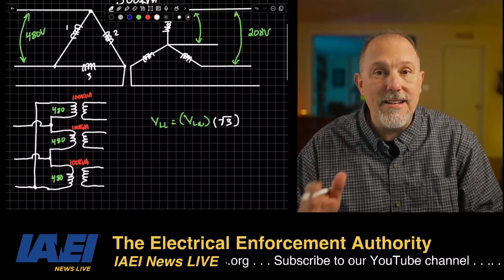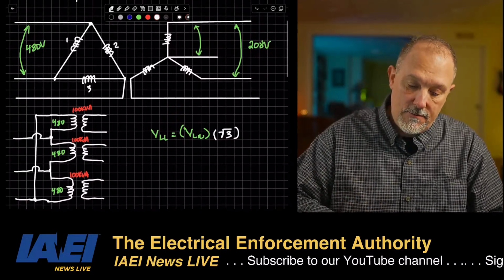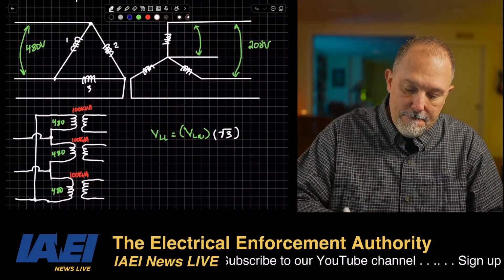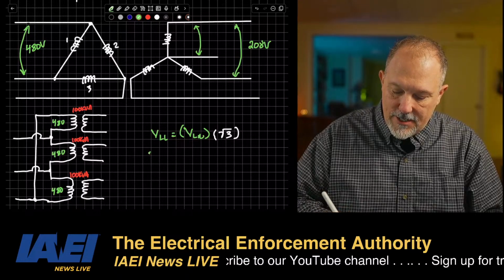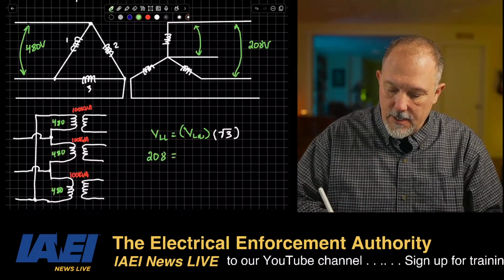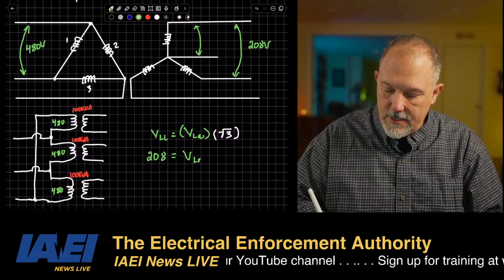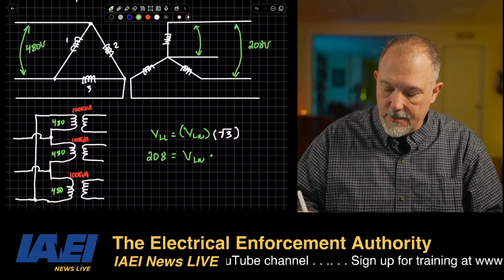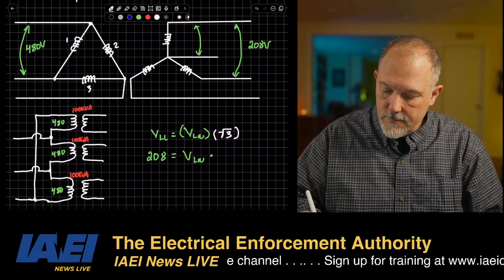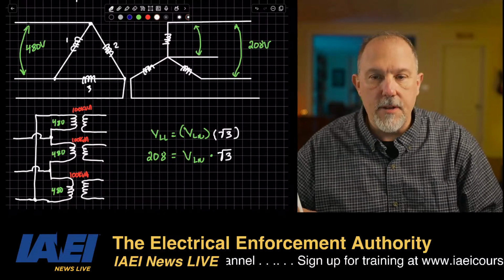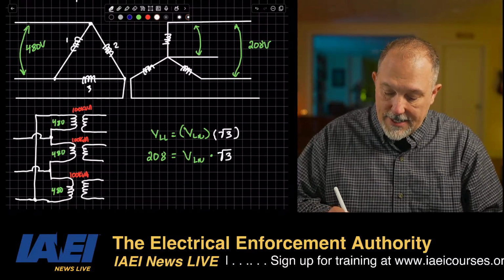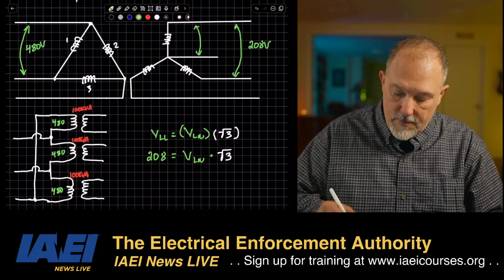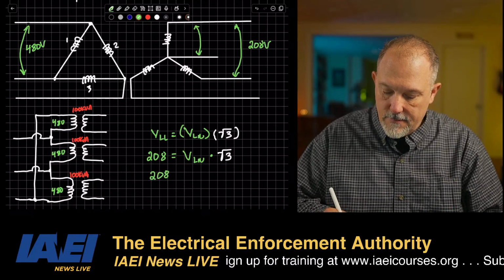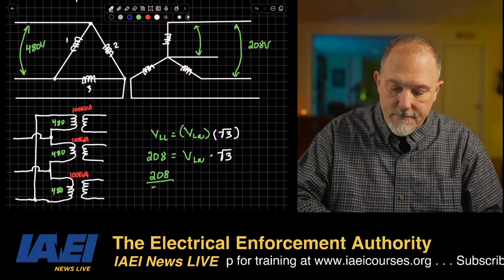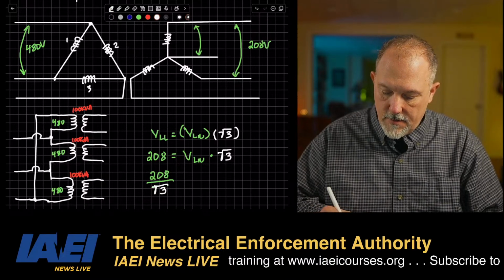If I know line to line is 208 volts, so I know 208 is equal to V line to neutral times the square root of 3. So V line to neutral is 208 divided by the square root of 3.